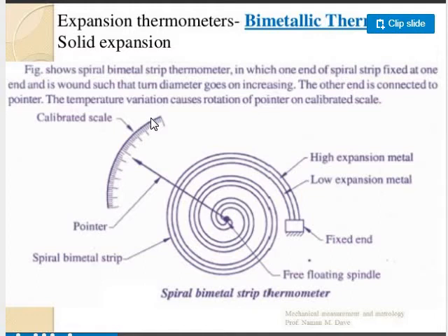So I think you will now have understood the concept. When this device is fixed where we need to measure the temperature, based on the change in temperature, this bimetallic strip will change. Its dimension is going to change. In the bimetallic strip, what did we see? It will bend. The side where the low expansion metal is, the strip will bend toward that side. The high expansion metal will expand more compared to the lower metal. So the same concept, we have the high and low expansion metal.